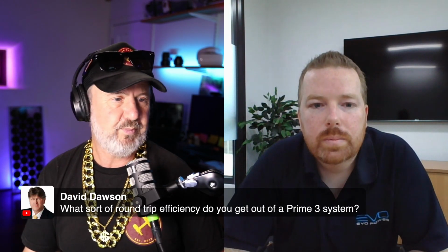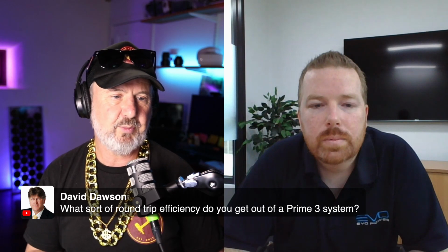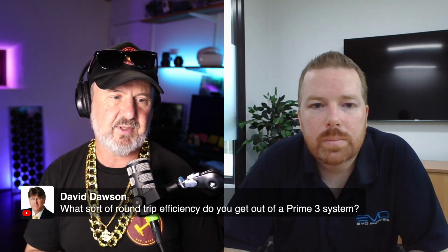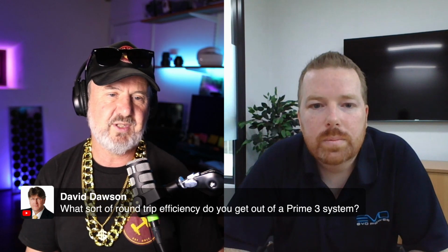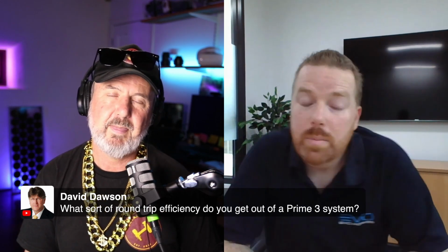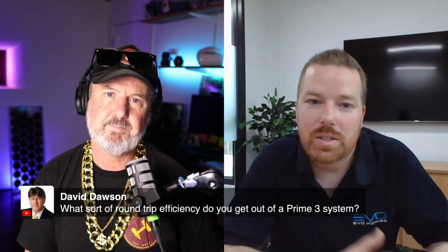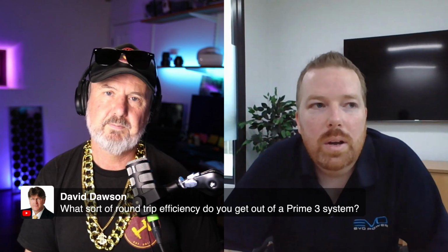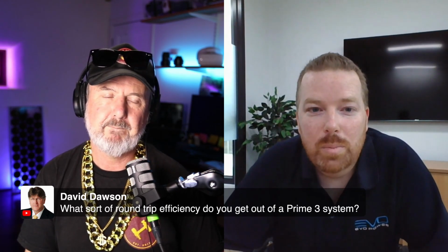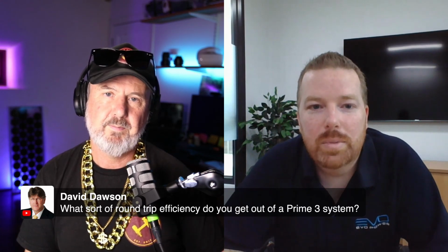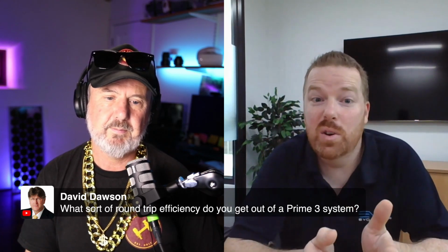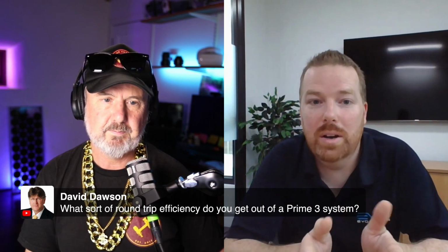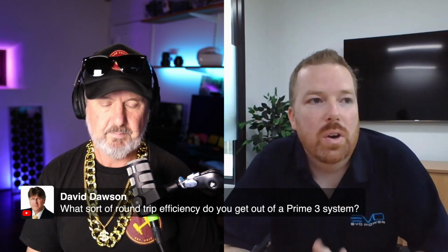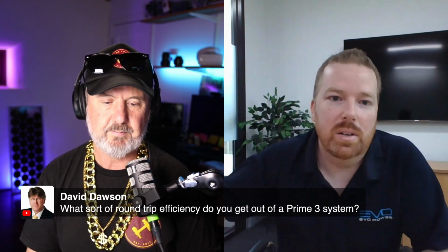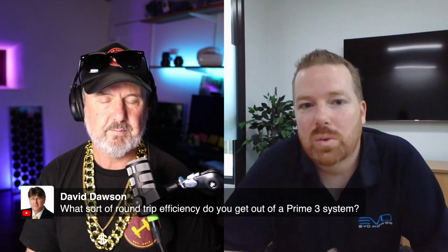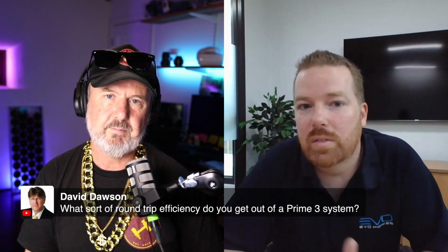David's brought in another point - what sort of round trip efficiency do you get out of a Prime 3 system? Do you want to define round trip efficiency? There's different figures on the AC side and the DC side - it depends on what power you're running at. Inverter manufacturers' data sheets will have a graph showing at 10% it's very inefficient, you may only get 10% of the power rating, it can be very low. When you get up to around 50% and greater, it's generally 95% or around that mark - that's what we're seeing for the SP Pro.